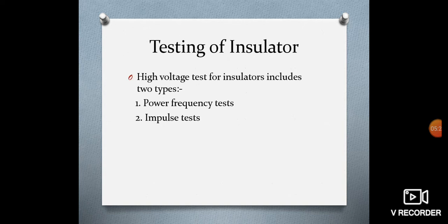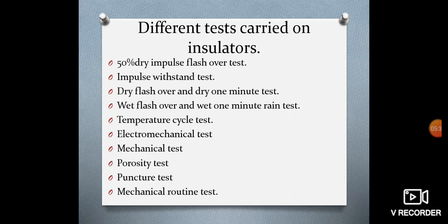Testing of insulators. The different tests carried out on insulators are power frequency tests and impulse tests. So we'll understand the different tests carried out on insulators. 50% dry impulse flashover test. This test is carried out on a clean insulator mounted as in normal working conditions. Impulse voltage of 1/50 microsecond wave shape and of an amplitude which can cause 50% flashover of the insulator is applied. That is, of the impulses applied, 50% should cause flashover. 20 applications of impulse should not damage the insulator. Generally 20 applications of impulse voltage are carried out, and 50% dry impulse flashover should take place.